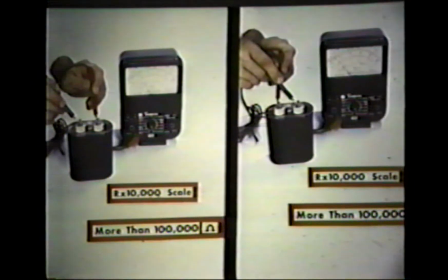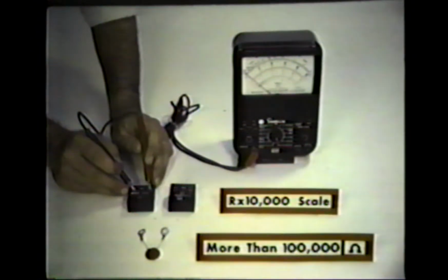The capacitor can be checked on the R times 10,000 scale. The meter needle should deflect towards 0, then swing up to more than 100,000 ohms. Switch leads, and the meter should repeat this charging up pattern. The filters or snubbers labeled 23, 22, or 25 recs can be checked in the same manner as the larger capacitor. However, the meter needle will deflect much faster for these smaller capacitors.